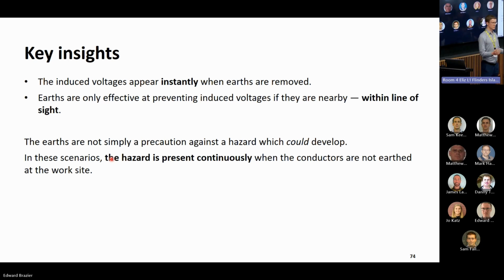We're not just talking about hazards that could develop rarely under special conditions. In the scenarios we looked at, the hazard is there continuously whenever the conductors are not earthed correctly at the work site. The hazard exists until the moment you connect the local working earth, and it appears instantly when you remove that earth.